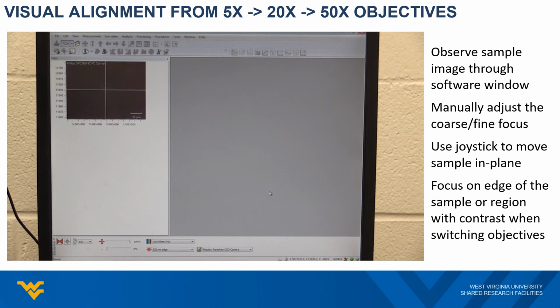For visual alignment, the image from the microscope will be shown on the upper left corner of the software window. You will need to manually adjust the focus knob and use joystick to move the sample in plane. This will allow you to obtain a sharp image and locate the region of interest. You should always start with the 5 times objective, which will allow you to locate your sample most easily. Once you have a sharp image from the sample using 5 times objective, you could focus on the edge of the sample or some regions with sharp optical contrast, then switch to the higher objective. This will make alignment using high objective much easier.